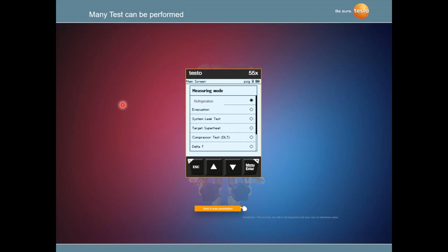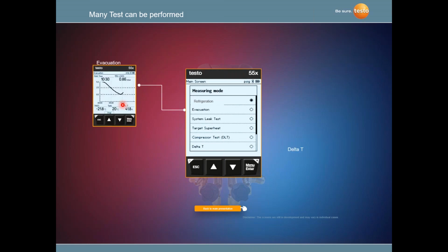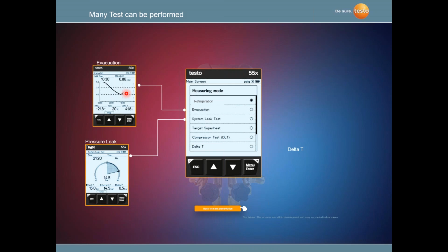So today's instruments, you can do a lot of different measurements. We talked a lot about superheat and subcooling and how we can do those simultaneously, but the screen can also show you the vacuum side, the evacuation side. So not only are we measuring in microns by using a smart probe, a wireless vacuum probe, a micron probe, but we're also showing a graph of how those microns are falling and holding over a period of time. We have a pressure leak test, a very common test that everybody probably uses nitrogen for to check if there are any positive pressure leaks. Putting 300 psi positive pressure on a system and then seeing, because there's a built-in clock in the instrument, if there is any change in pressure over time.